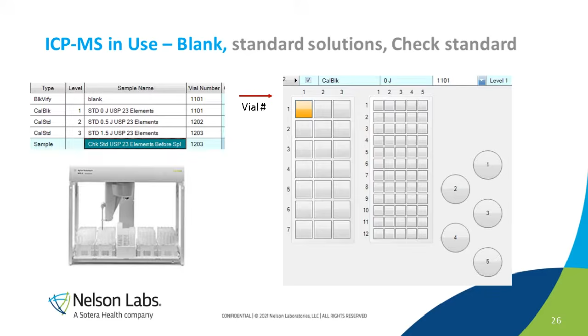Now, from here, using the auto sampler, we deliver into the ICP-MS. So now it turns to the standard portion, and we are injecting standard solution, and as you can see here, the 0.5 to 1.5 element standard solution is injected from here. And then since this one we are talking about, see here 23, I'm going to tell you later about this part. We were supposed to use 24, and then all of these give linearity, and the specification is over 0.99, all passed.